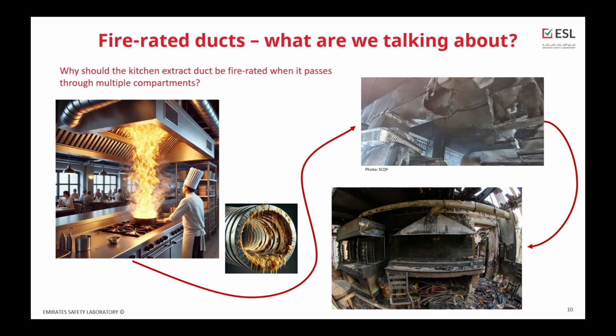this is a good recipe for fire, because during the operation of the kitchen in commercial use, the grease is accumulating inside the extraction system. If the grease is big enough, and when this grease accumulation is exposed to the heat or direct flame which is pulled into the system, the grease may catch fire and cause a lot of problems, huge fatal consequences.